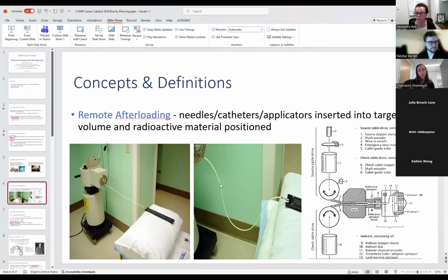And at any point in time, if the afterloader is executing something called a treatment plan, it knows, for example, that I'm going to have to go to channel number whatever. Let's say channel 1, I'm going to have to go out to a particular distance from the index surface, and that's usually how it's measured. So, let's say 1,254 millimeters. I'm going to go 1,254 millimeters from the index surface, and I'm going to pause a certain amount of time at this position, and then move to a different position, and so on.